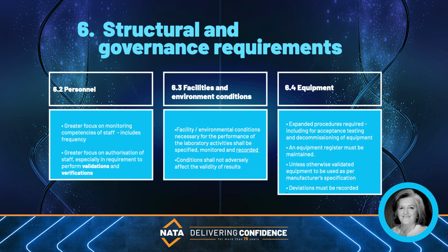Equipment shall be uniquely labelled or identified, and an equipment register shall be made, which was not a previous requirement. Of note, equipment includes the hardware and the software, the measuring systems and the lab information systems, and the sample transport systems, including hospital pneumatics and lines.